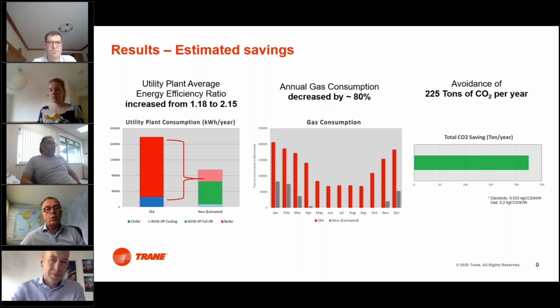So the energy ratio went up from 1.18 to 2.15, so that's almost double. And consequently, the annual gas consumption decreased by about 80% by connecting those dots for the capacity that we could cover with this system. And at the end of the day, the avoidance of CO2 footprint was quite impressive with 225 tons. And that is only by opening up the discussion from a simple chiller replacement to connecting the dots and creating a heat pump system in this process system.